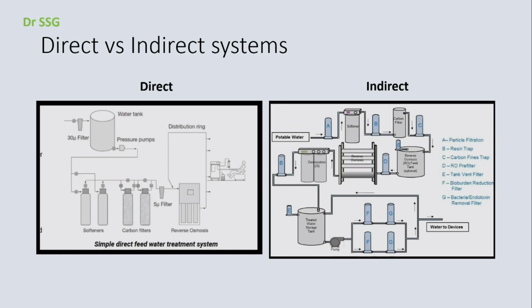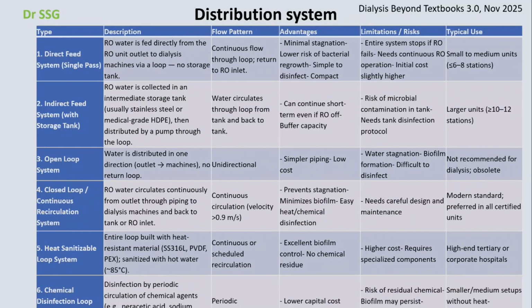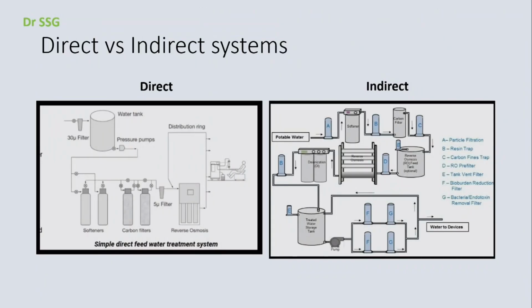We do not use the single chain. Because if it is a single chain, without a loop, then it becomes stagnant. When the unit is closed, it would be a stagnant system and therefore there is biofilm formation. So it's always a loop, direct or indirect. Indirect helps because the RO tank will serve a purpose wherein the machine is offline and we need to still sustain the unit. There are multiple advantages. There are others also, that the heat sanitizable loop, also the chemical sanitizable loop. So we'll come to that forward.